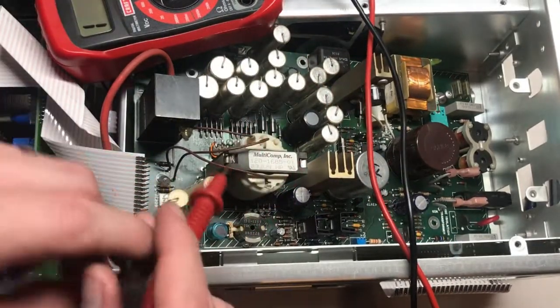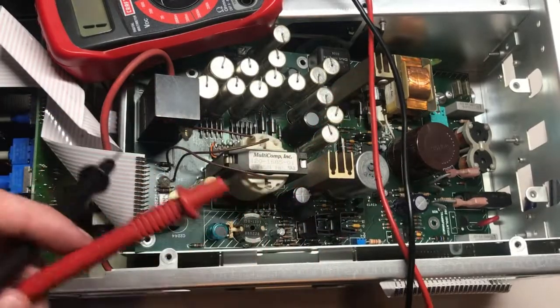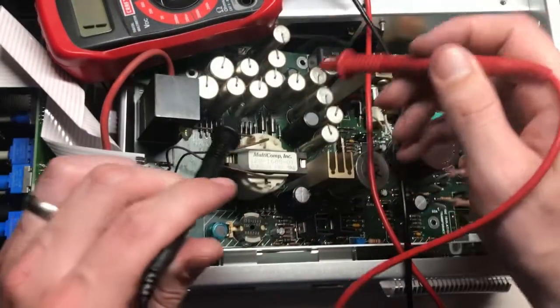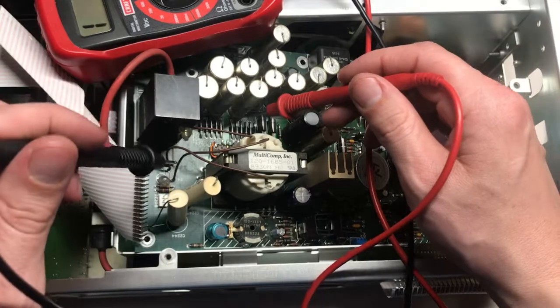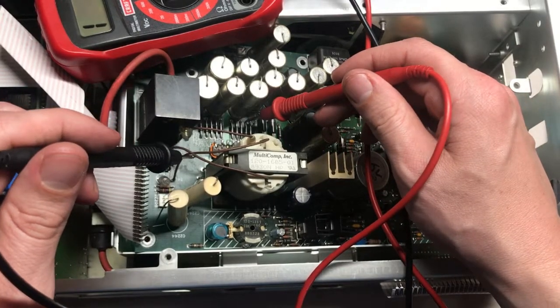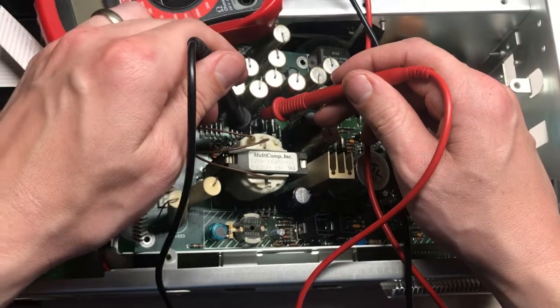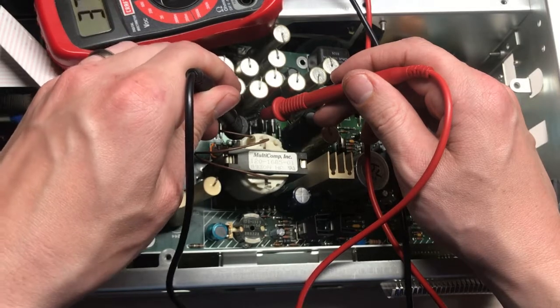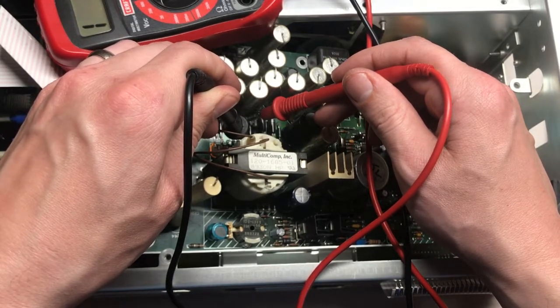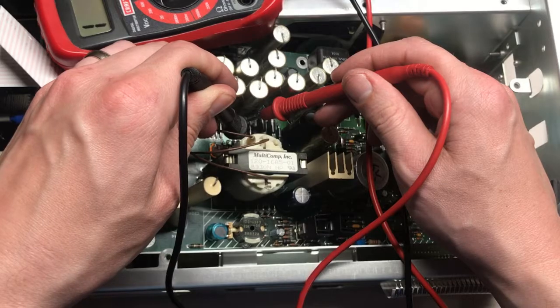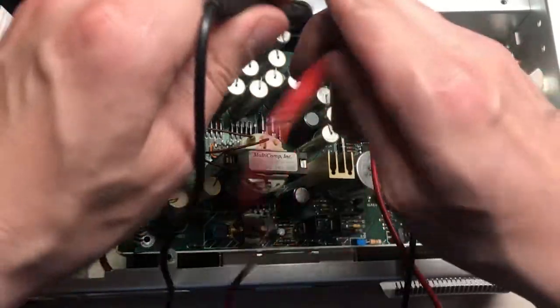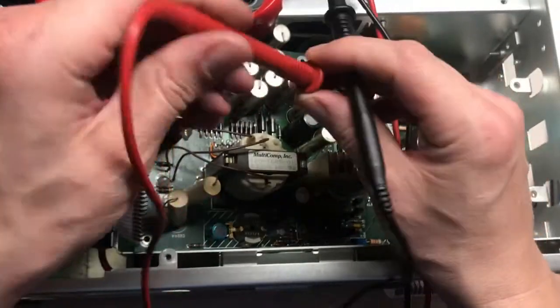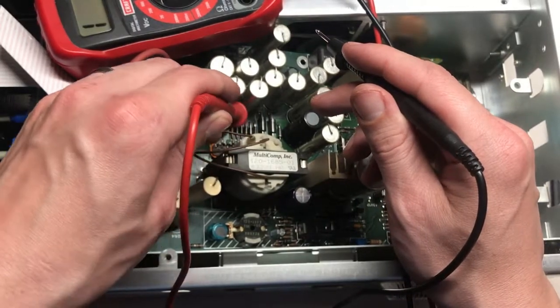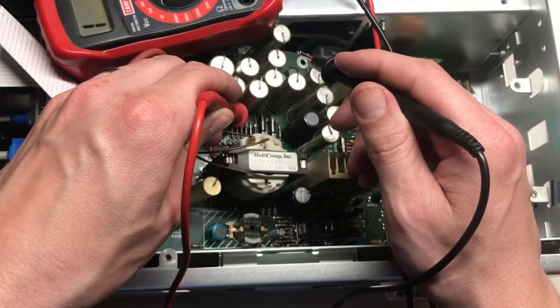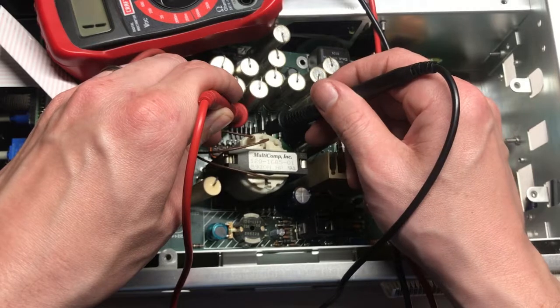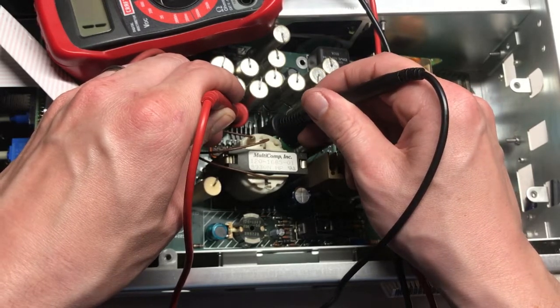Ideally, I'd have this out of the board, or out of the unit, but I don't think that's really possible with the high voltage transformer. So here's the diode here, one leg, and another leg right there. All right, so it's open with that polarity. Let me check the other polarity here. So obviously we should be open in one side and around 600-700 millivolts to the other side. Let's see here.